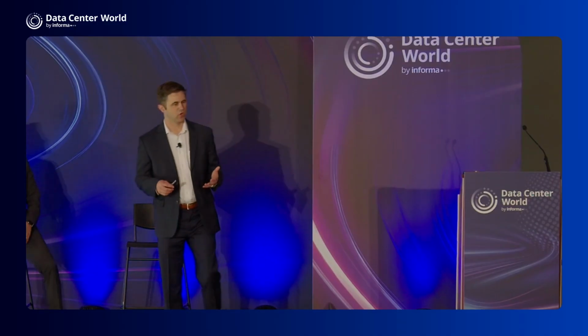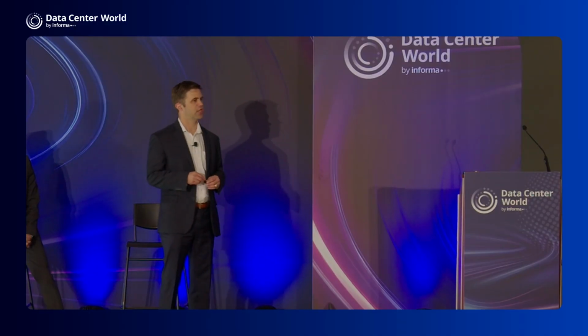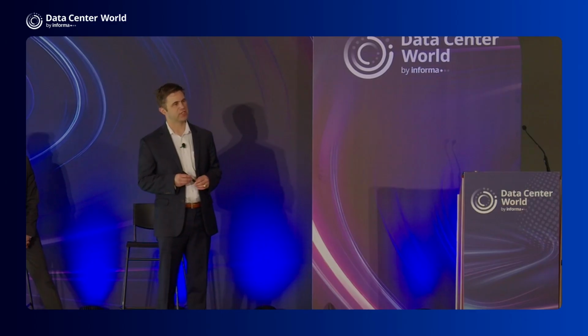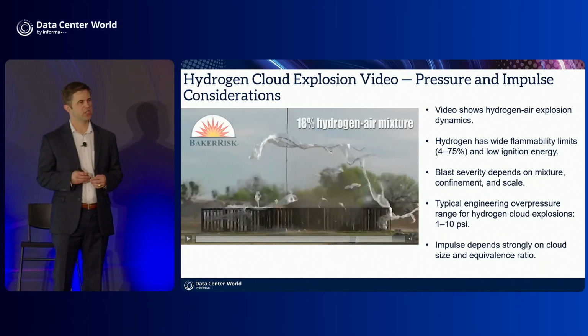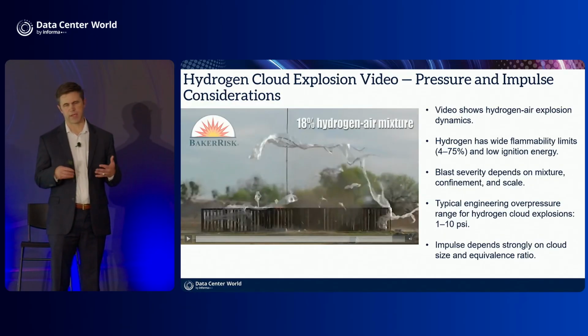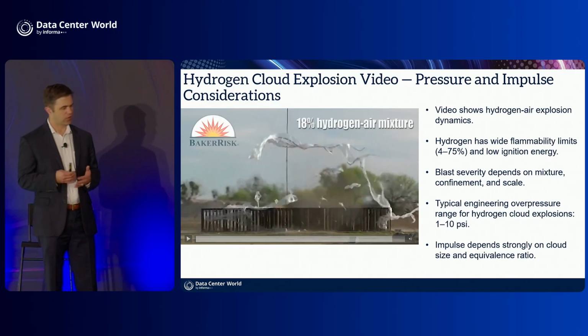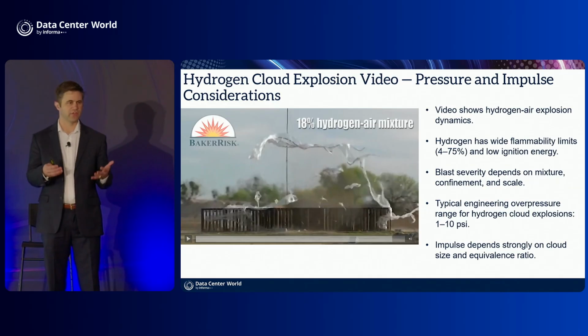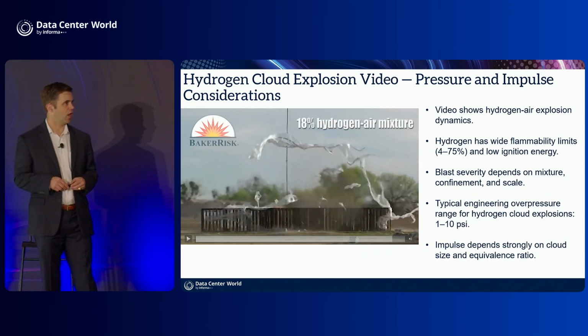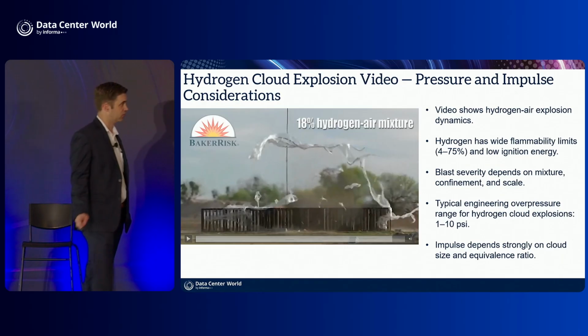In industry, we've heard of projects looking at using hydrogen as a clean source of energy to fuel generators or backup generators. Bringing this type of fuel on site presents a more severe hazard than using natural gas, with loads that could be applied to the building structure much greater than what would be relevant for natural gas supply.